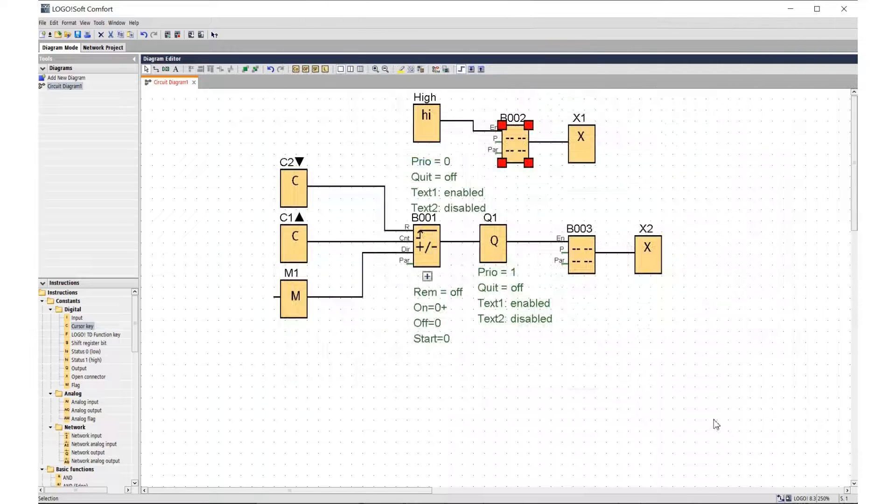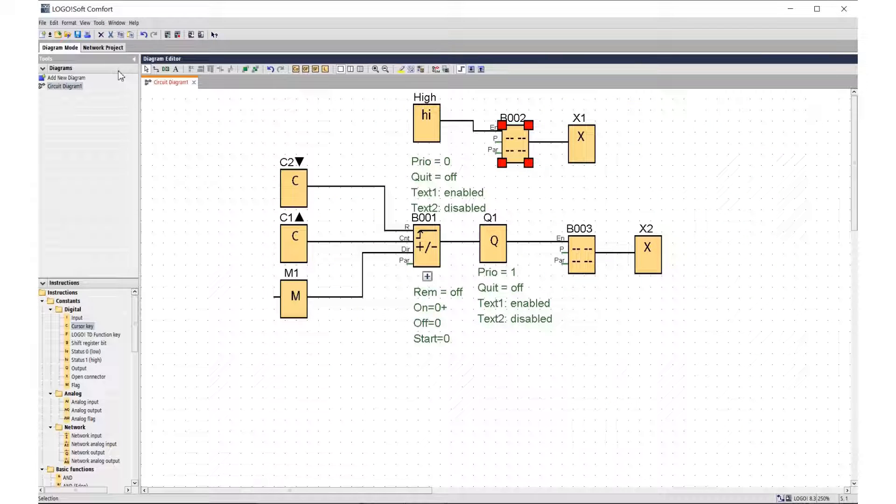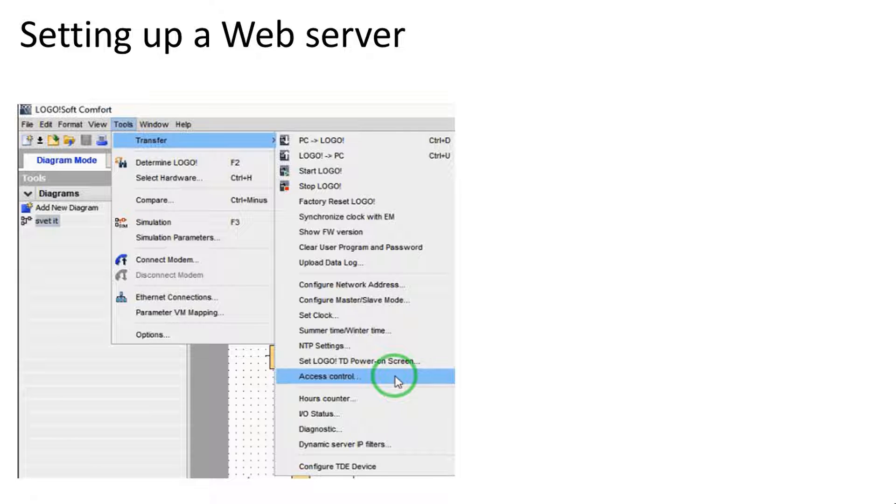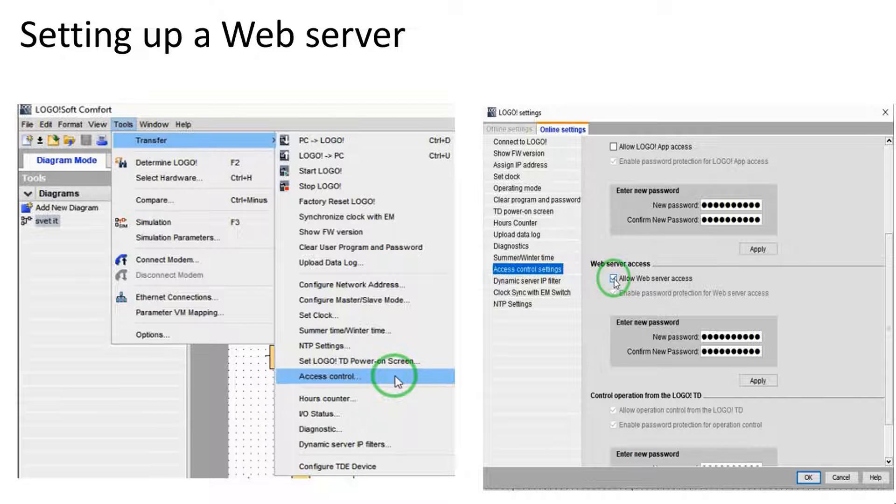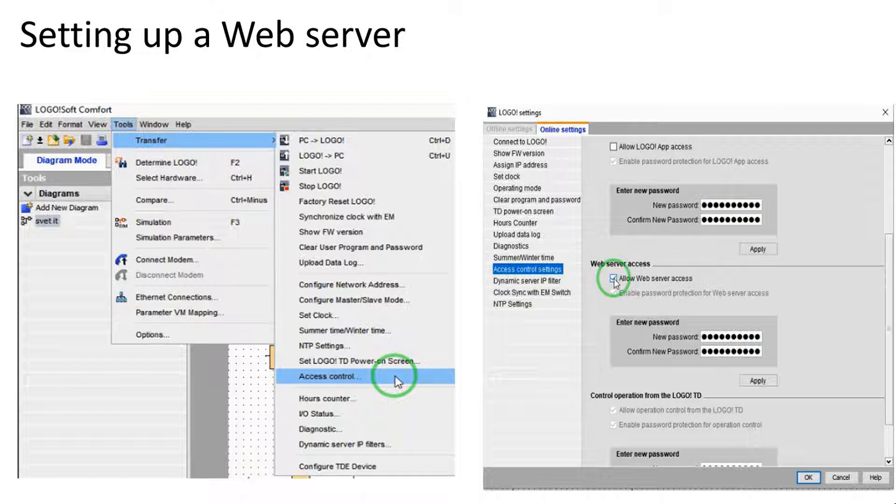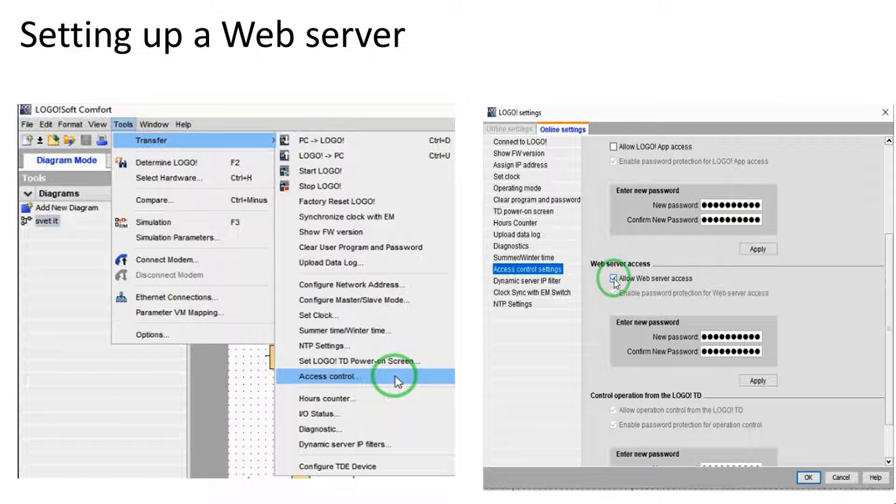Now you need to load the controller. Web server settings are made before loading the project into the LOGO! module. Go to the Tools Transfer tab and select Access Control. The web server configuration window appears. In the access control setting tab, check the box that allows the server to work: Allow web server access. Enter a new password and click Apply.